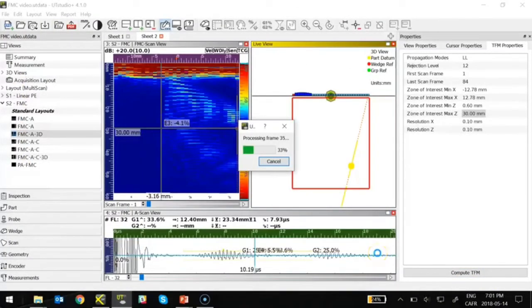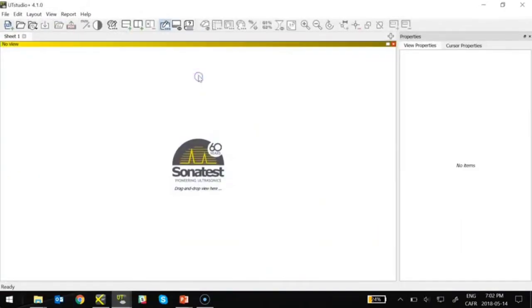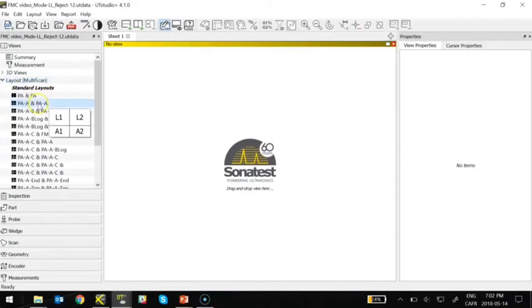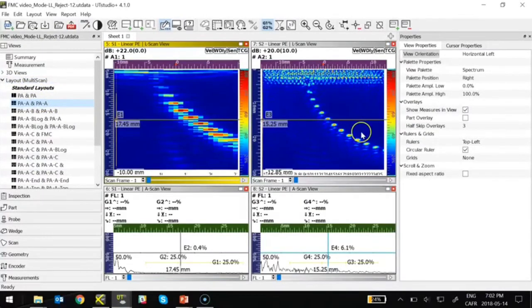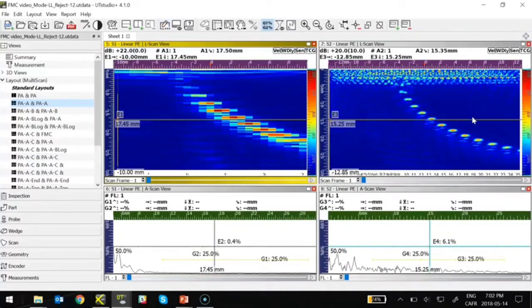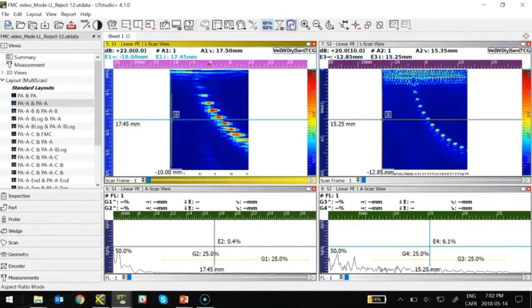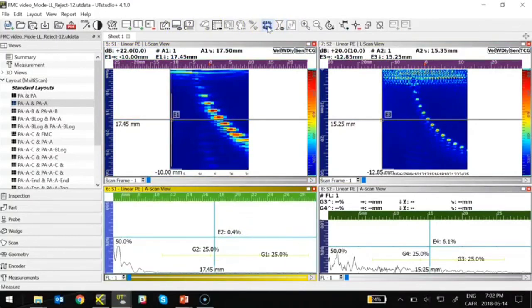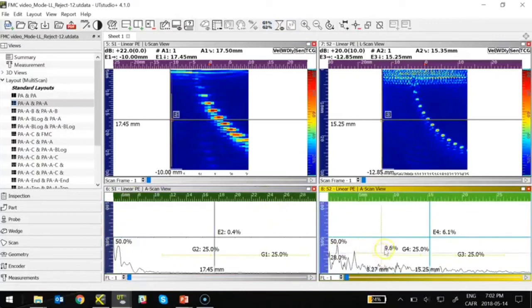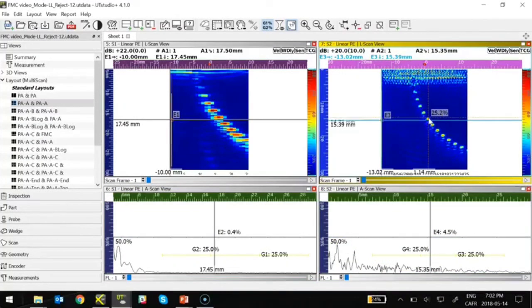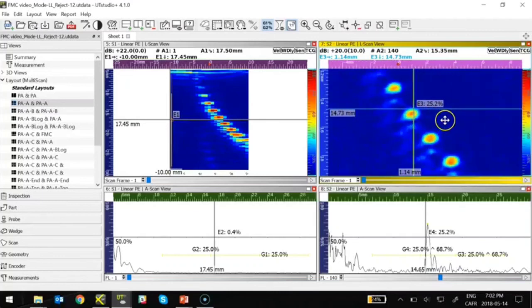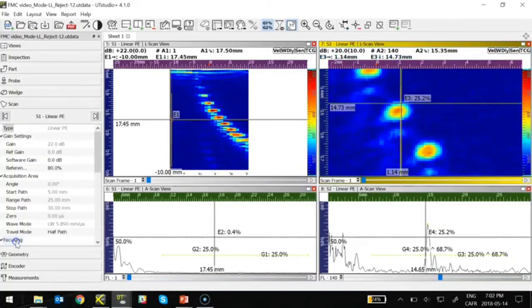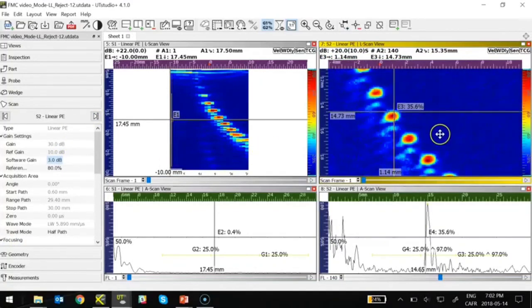Now, computing my TFM images, I use the LL mode, and I'm computing directly under the probe. By doing that, I'm creating a new set of data files, so a new UT data, having the TFM images in it. Now we can see here on the right that I have my TFM images, but also on the left that I still have access to my phase array scan. So on the left I have my phase array scan, and on the right I have my TFM scan. And the interesting thing here is that I can compare both defects cut by a phase array and TFM and compare the analysis side by side.